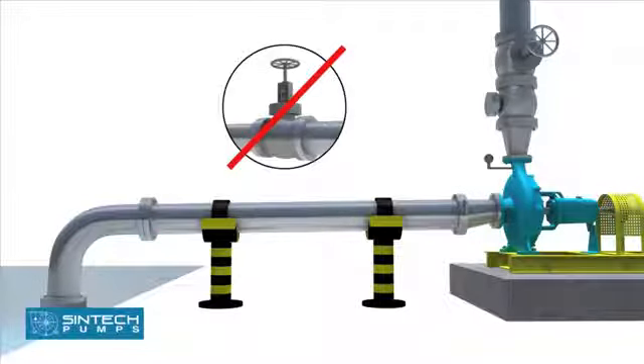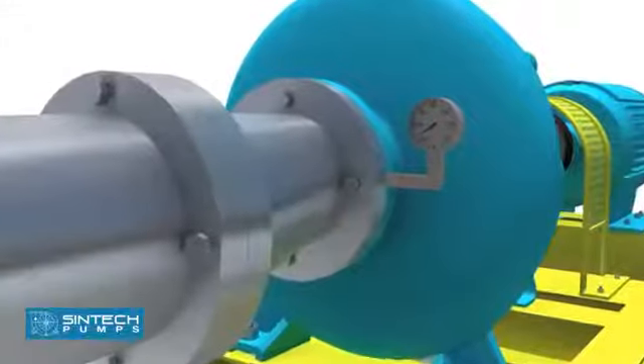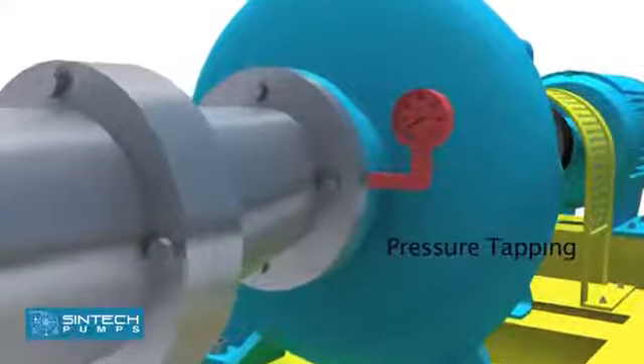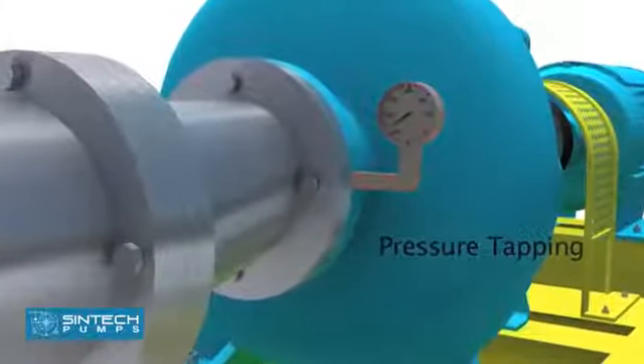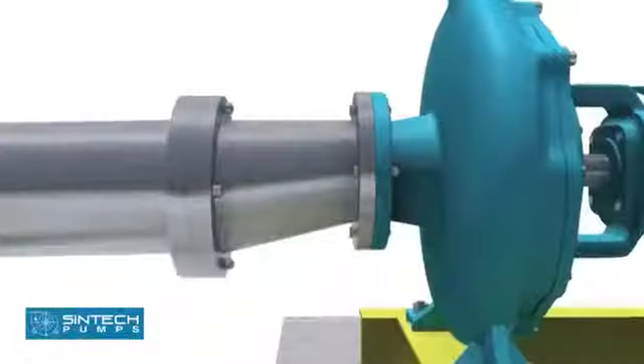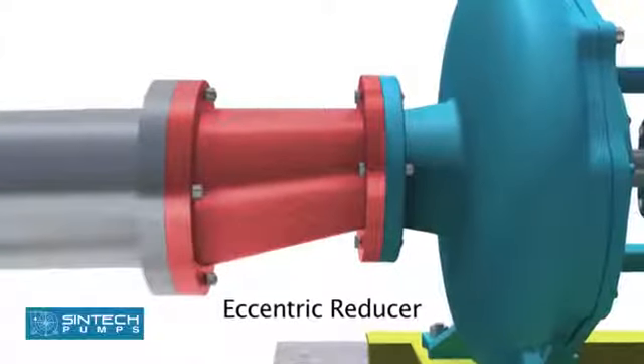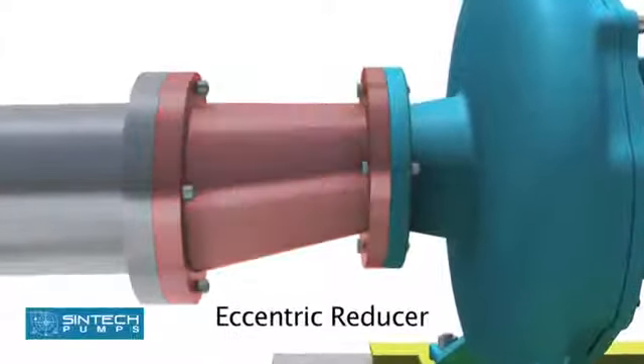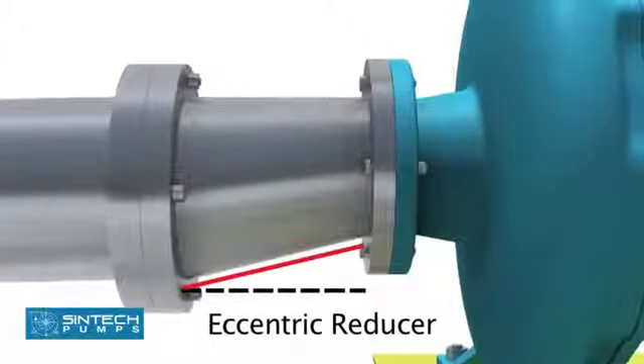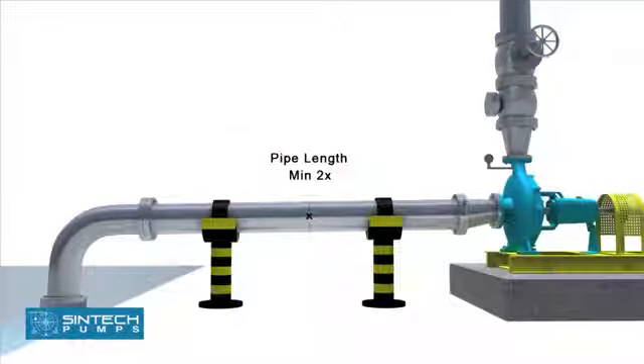No isolation valve is recommended. There should be a tapping provided for installing a vacuum gauge in the suction line. The reducer joining the straight length of pipe in the pump line should be an eccentric reducer with the inclined side as the bottom side. The straight length of pipe after the eccentric reducer should be 2 times the pipe diameter.